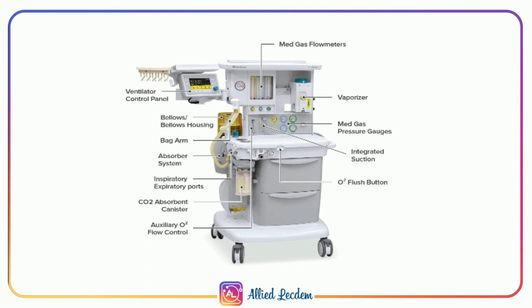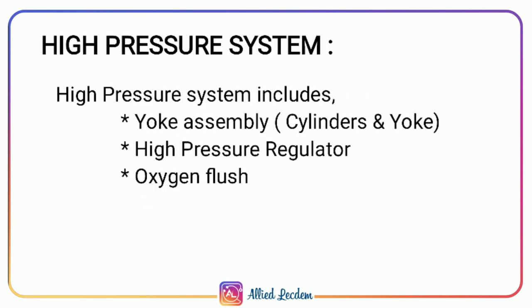Soda lime is the substance that filters the exhaled gas from the patient. Other components include auxiliary oxygen flow control, medical gas flow meters to adjust and control the rate of flow of gases, a vaporizer for inhalational agents, medical gas pressure gauges, and an integrated suction and oxygen flush button for forceful administration of oxygen during emergency.